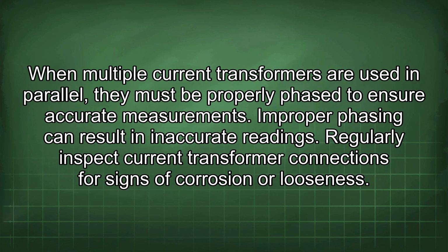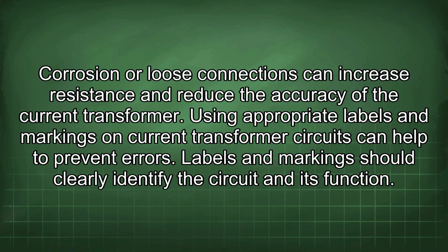When multiple current transformers are used in parallel, they must be properly phased to ensure accurate measurements. Improper phasing can result in inaccurate readings. Regularly inspect current transformer connections for signs of corrosion or looseness. Corrosion or loose connections can increase resistance and reduce the accuracy of the current transformer.